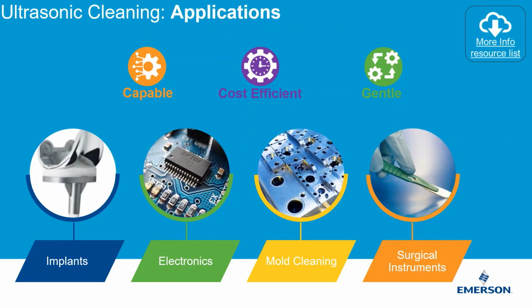Ultrasonic cleaning is another widespread use of high-frequency ultrasonic acoustic vibration, whereby the acoustic vibrations are introduced into a cleaning operation. This is a well-defined industrial cleaning process widely employed in medical device manufacturing. It's particularly effective in cleaning small, intricate parts, hard-to-reach blind holes, and to accelerate surface treatment processes. This is a cleaning process, and it shouldn't be confused with a sterilization process.